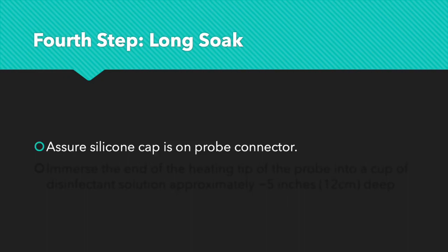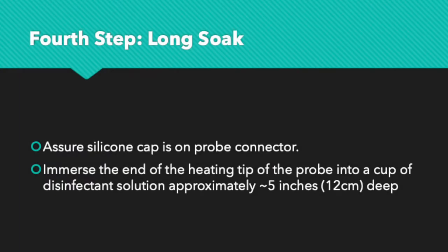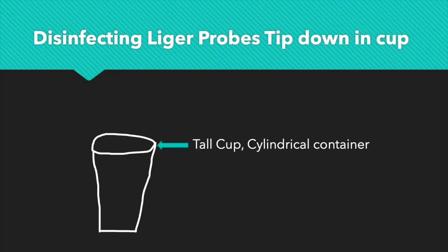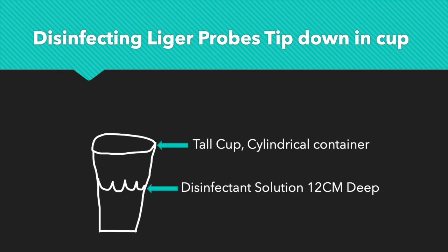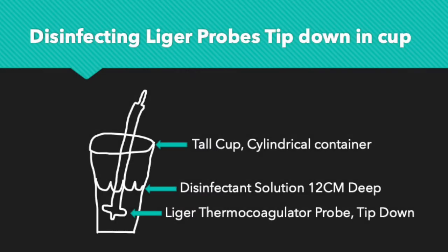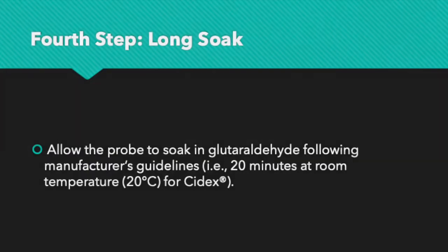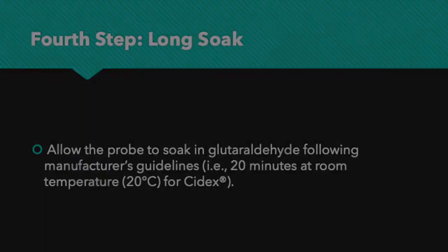Again, assure the silicone cap is on the probe connector. Then immerse the end of the heating tip of the probe into a cup, not a basin, of disinfectant solution that's approximately 5 inches or 12 centimeters deep. Make sure that the heating end of the probe is facing down into the disinfectant solution. Allow the probe to soak that way in glutaraldehyde following the manufacturer's guidelines, for example 20 minutes at room temperature.